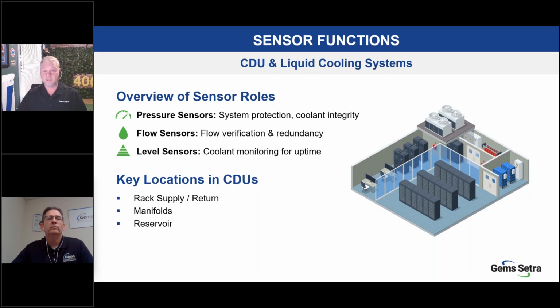For pressure, we commonly see dual pressure sensors at the supply and return lines to monitor differential pressure in coolant distribution units. Our flow sensors are for continuous monitoring and switches for low flow indication, and level sensors can be found for high or low level indication in coolant reservoirs and at top of rack manifolds to ensure all servers are receiving coolant. Now it says locations in CDUs here, but our GEMS products are found throughout the facility water systems, or FWS, and the technology cooling systems, or TCS, in the data center facility. These are also called the primary and secondary loops.